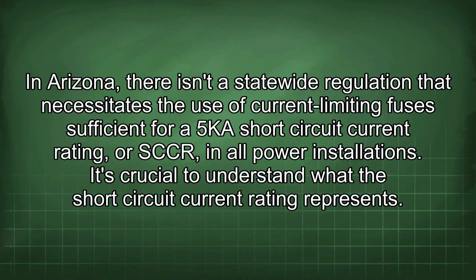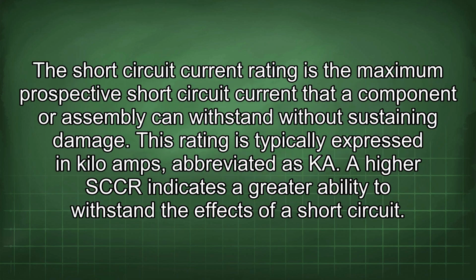Arizona, there isn't a statewide regulation that necessitates the use of current-limiting fuses sufficient for 5KA short-circuit current rating, or SCCR, in all power installations. It's crucial to understand what the short-circuit current rating represents. The short-circuit current rating is the maximum prospective short-circuit current that a component or assembly can withstand without sustaining damage. This rating is typically expressed in kiloamps, abbreviated as KA. A higher SCCR indicates a greater ability to withstand the effects of a short circuit.